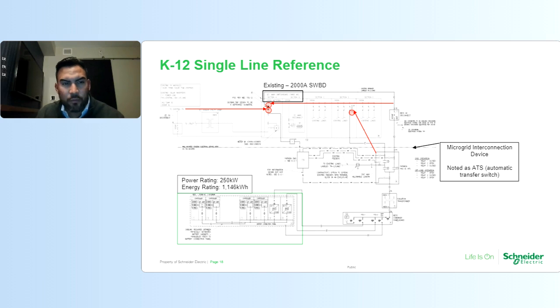Now, if you see here, I've highlighted some red dots throughout the single line diagram. This shows you just the points of interconnection. This project happened in California. Most utilities prefer not to have multiple points of interconnection. They want just one. So what SourcePack was able to do in this design, we eliminated two of these additional points of interconnection and just connected directly to the main service breaker here, which was a preference for the utility for simplicity and easy approval. And that's the microgrid interconnection device highlighted. Now, I also want to highlight here that this doesn't replace that BESS disconnect switch. You still require that per code to disconnect and provide service and maintenance to your inverter-based resources. So that was still included there.